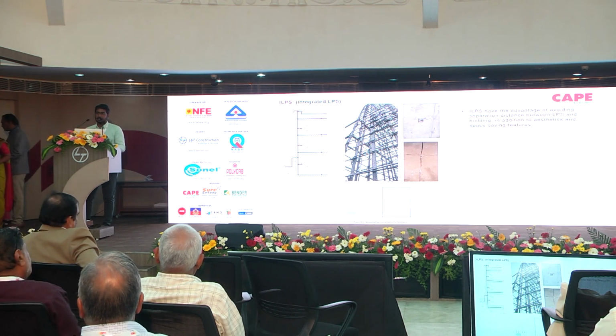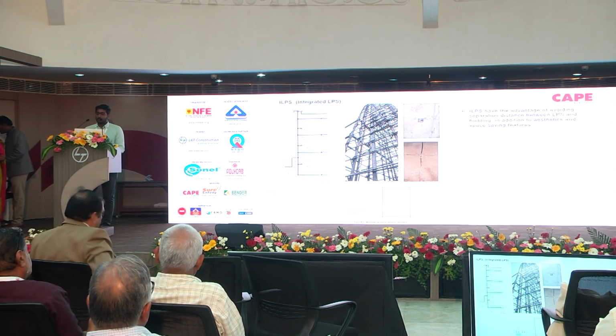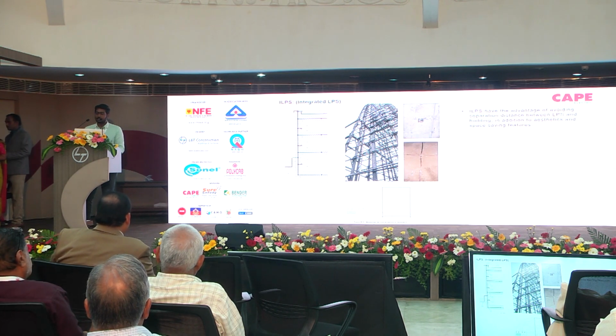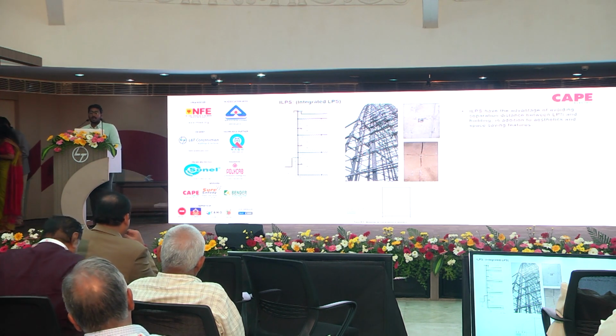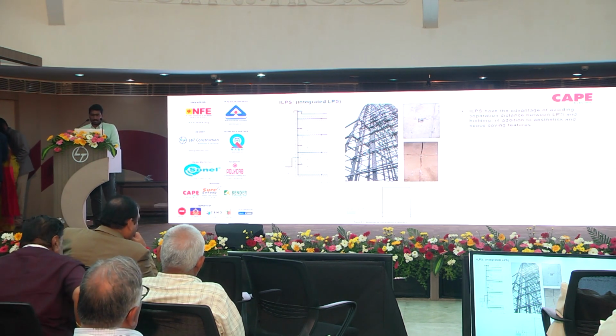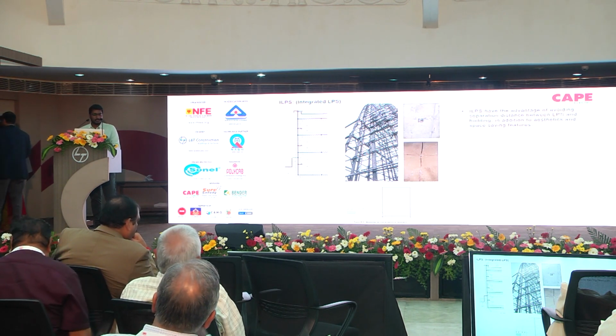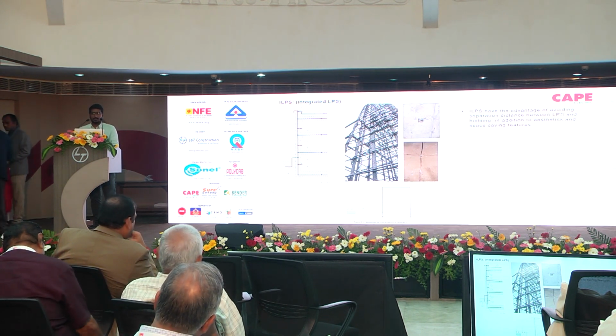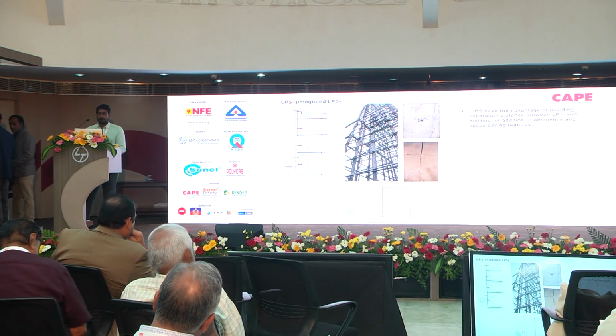Coming to ELPS, in the previous session it has been explained about separation distance. So ILPS, which we term as integrated lightning protection system, has the advantage of not having to maintain a separation distance between the conductors and the building. This is just a pictorial representation of that, and these are a few installation photos where the conductor is laid as a mesh at the soil level, and from that a connector is raised to the column, and these are the stud points which are used for the continuity resistance test, and the continuity resistance should be below 0.2 ohm.